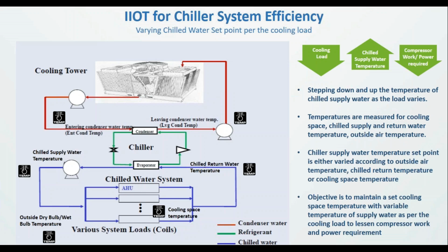Before that, recall the recommendation that improving chiller system efficiency can involve looking at the chiller supply water temperature. If we can monitor the cooling load in real time, there are different ways to do this: measuring outside dry bulb or wet bulb temperature, or tracking the number of people in a confined space via entry-exit points. With ASHRAE tables and logic built into the platform, we can accurately establish the real-time load for that geolocation.